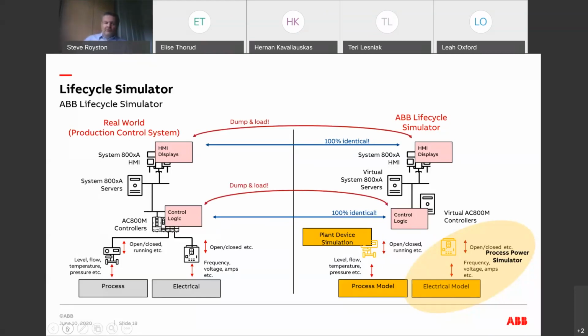The real benefit of having such a simulator, where we're emulating the real system, is that we can dump out the control logic from our programmable controllers and the HMI graphic displays from the real-time production system, and load them straight into the simulator system. This is because we're effectively running the same firmware in both environments, and the process of dumping out from the real world system and loading into the simulator is extremely quick - there's no new coding to be done in the process.